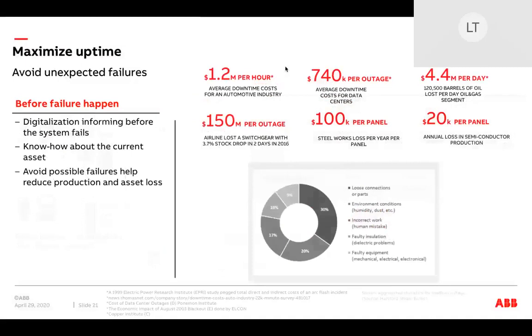Next, let's look at maximizing the uptime. With digitization-based maintenance, the system will inform you before an asset is about to fail, and it will allow you to plan when to change, upgrade, or modify the asset. Without this, let's consider you lose a charging motor on a medium voltage breaker. Let's say it happens on Christmas Eve. So the cost of the motor is, let's say, $100, yet the cost of labor at Christmas might be $2,000. If you'd planned this and you knew about it from condition-based and predictive maintenance, that could have been handled the week before to prevent those costs from occurring at Christmas and prevent all the overtime and additional costs for getting equipment to site.